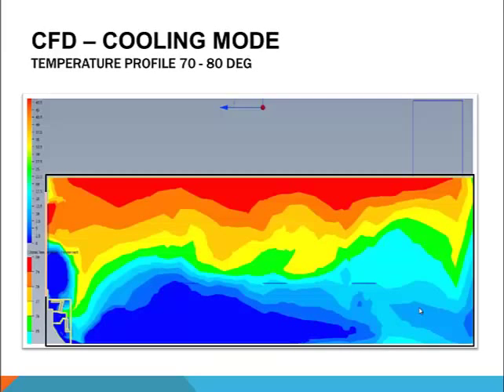Here is the result of the design cooling simulation. The floor mounted beam is discharging a cool mixture of air from the DOAS and room air in a vertical pattern to neutralize the perimeter glass load. You can also clearly see the cold mix of air extending into the interior of the room, with the displacement ventilation air pattern achieving good projection as it is drawn towards the simulated student loads. The dashed line indicating head level of the students is effectively the top of the occupied zone. Note the much warmer air at the ceiling level — this is typical for displacement cooling or any fully stratified air distribution system, where return air temperatures are higher because air volume requirements are lower but the same amount of heat is being removed from the room.